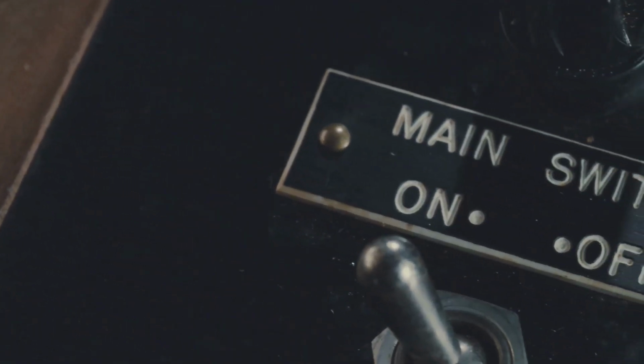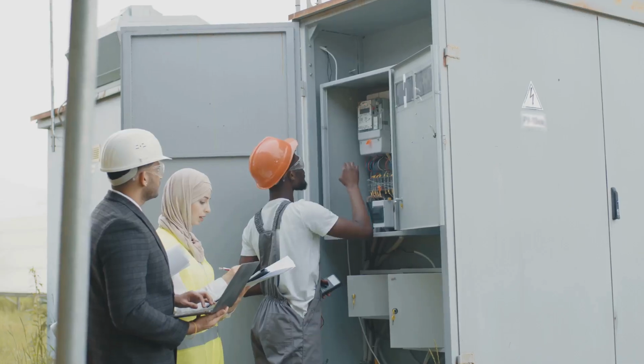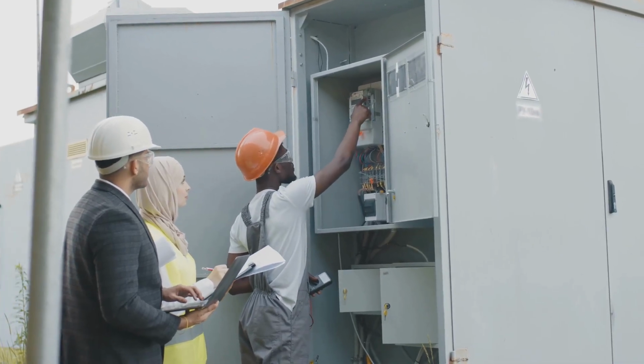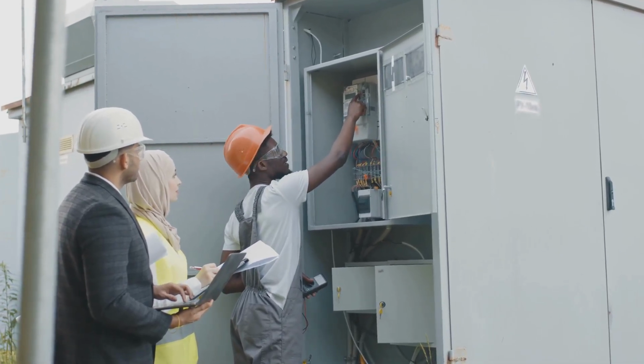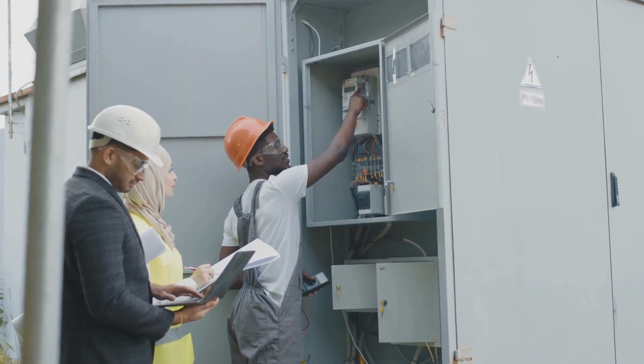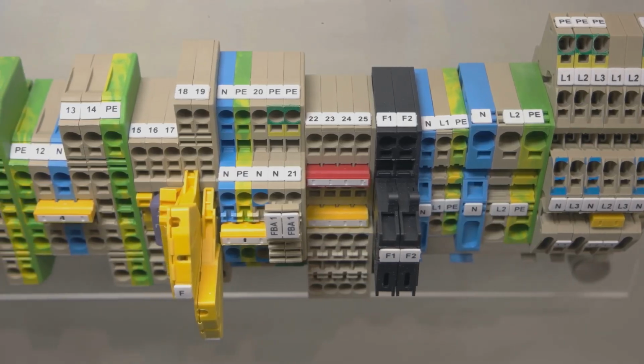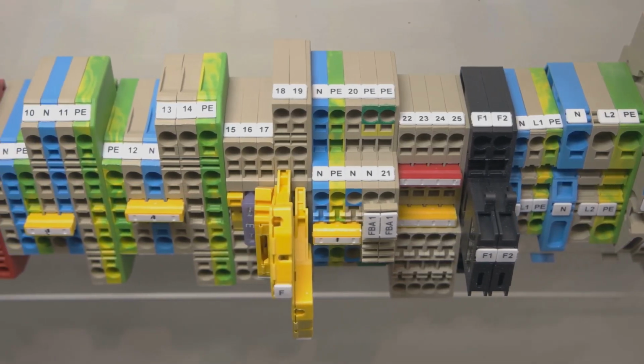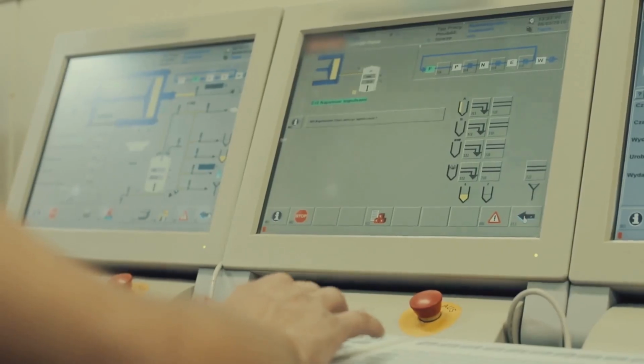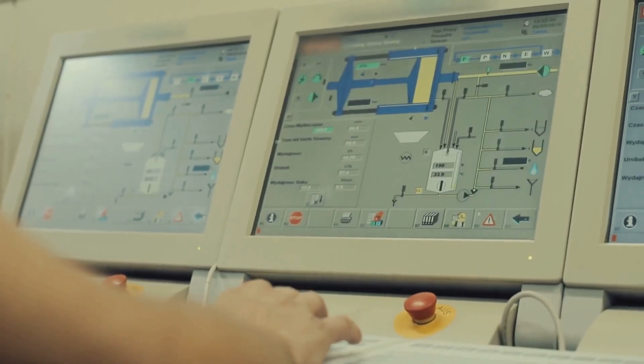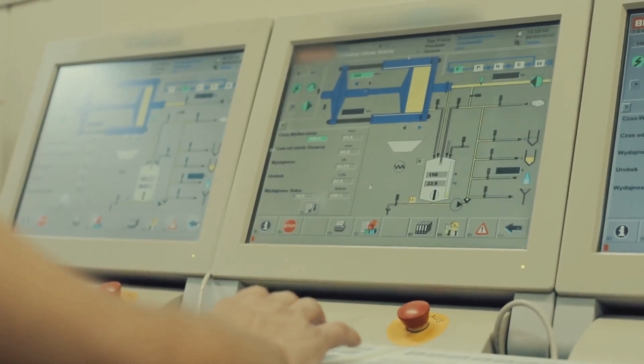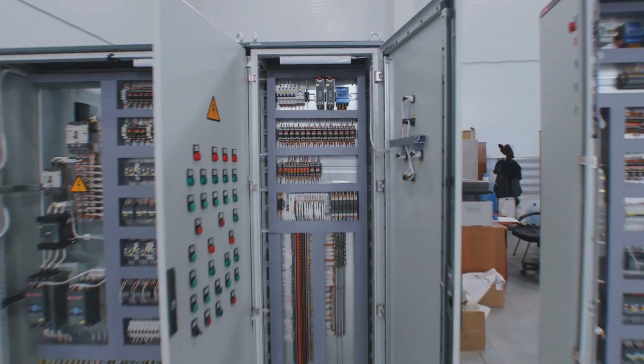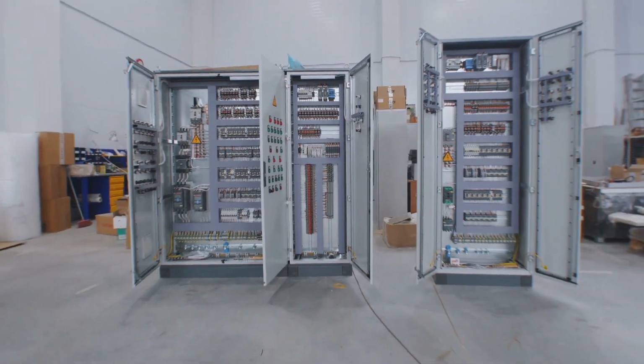Clause 4.3, Isolation Mechanisms. Each DER must include a visible, lockable means of disconnect, allowing utility personnel to safely isolate it. While this is a manual safety requirement, it also interacts with automated FRT logic. For example, the DER's software should not initiate disconnects based on minor disturbances. It should distinguish between transients to ride through and real faults to trip safely.